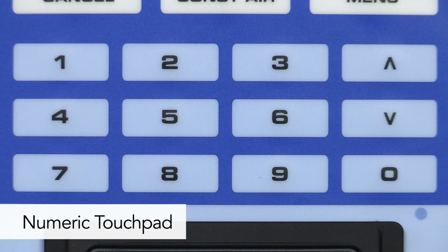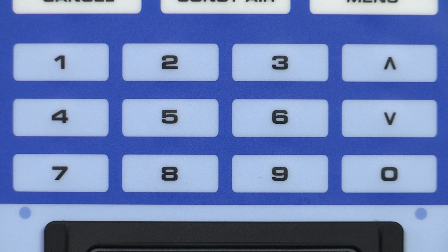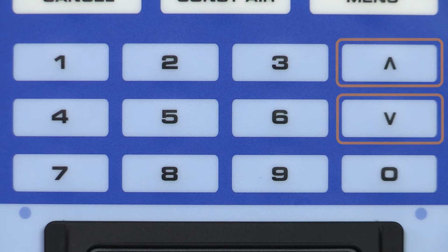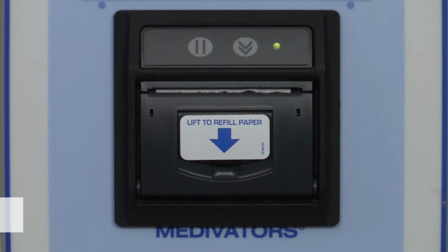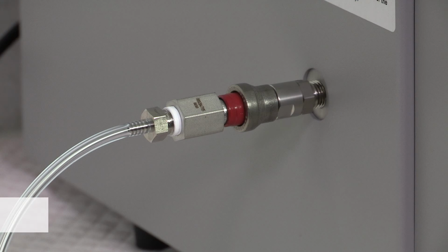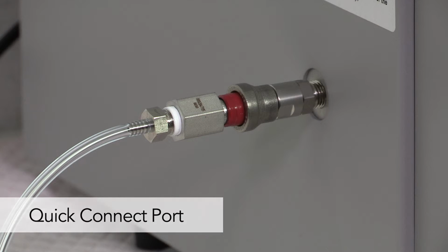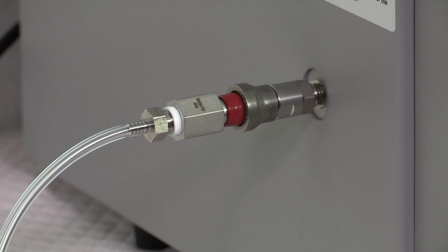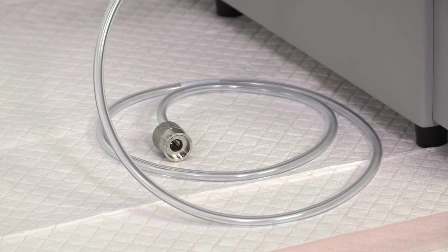The numeric touchpad is used to enter specific data, including endoscope serial number, operator ID, or patient ID information. The up and down arrows allow you to move through subroutine processes. A built-in printer provides printouts of test results. The Quick Connect port located on the side panel is used for attaching the Quick Connect tubing. The other end of the Quick Connect tubing attaches to the endoscope's leak connector.